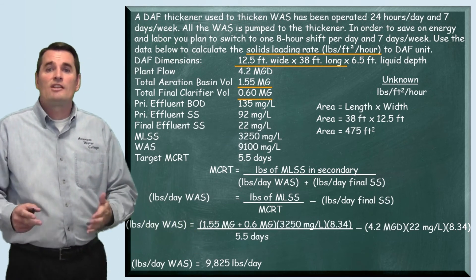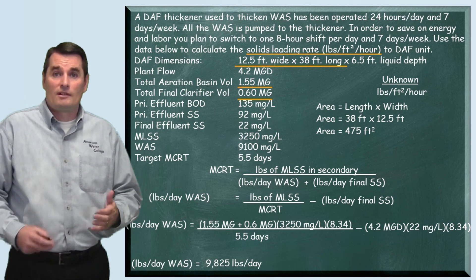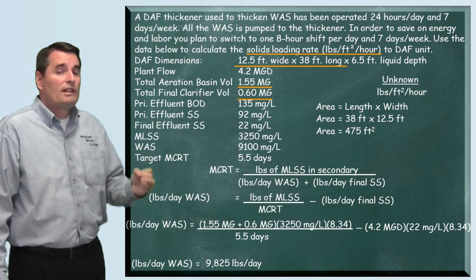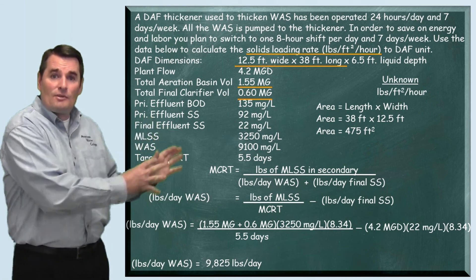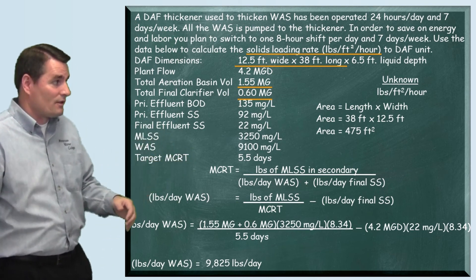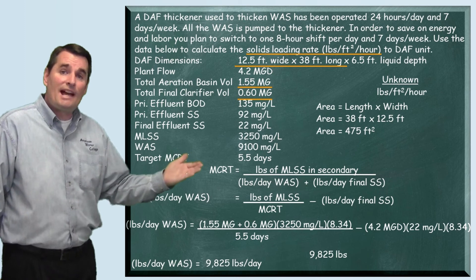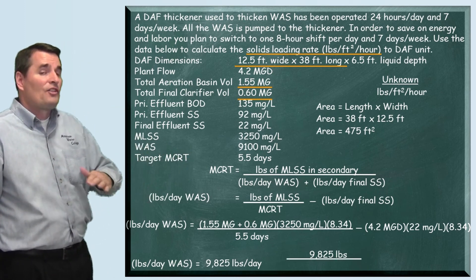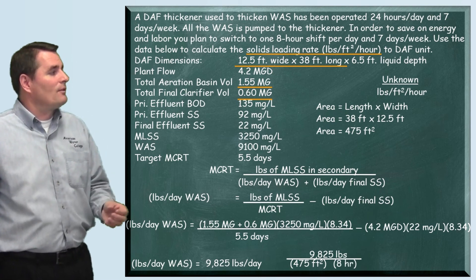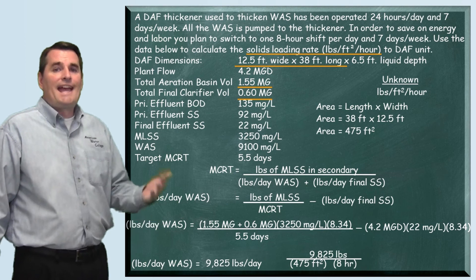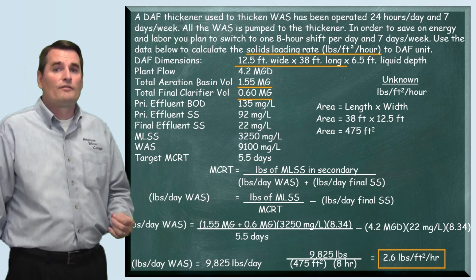The problem has us doing a change in operation. This is how many pounds per day we're producing going to the thickener, but rather than working on a 24-hour, seven-day-a-week cycle, we're switching to eight hours per day, still seven days a week — cramming all of this into an eight-hour shift. So we take the 9,825 pounds per day, divide by the eight-hour shift and by the surface area of 475 square feet, and we find that the solids loading rate is 2.6 pounds per square foot per hour.